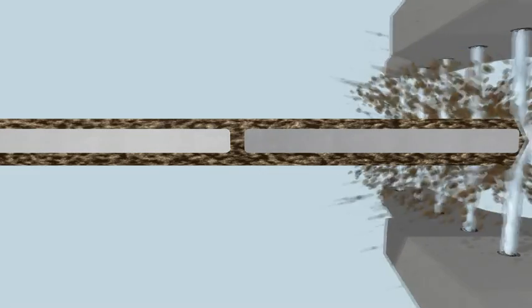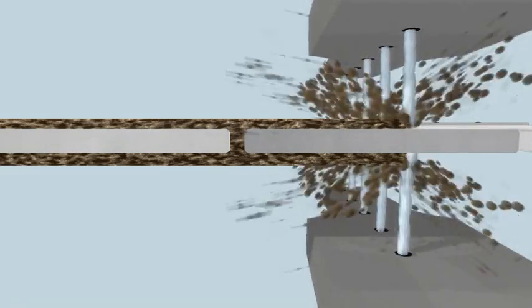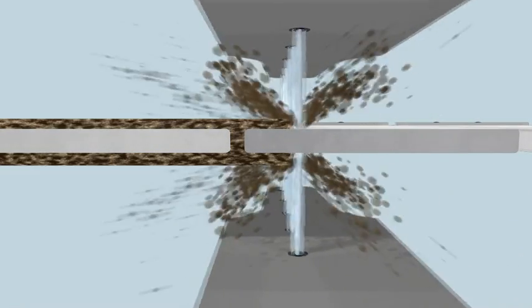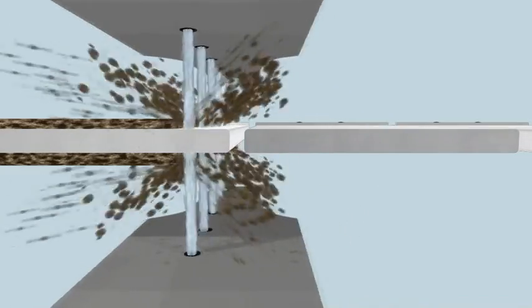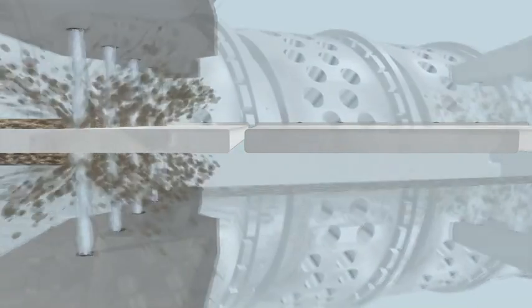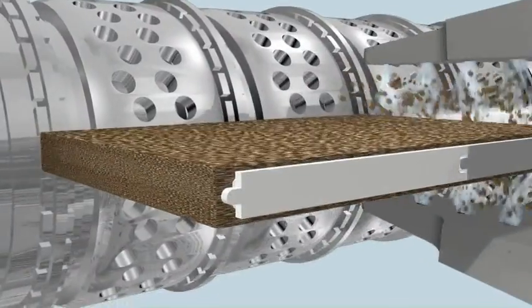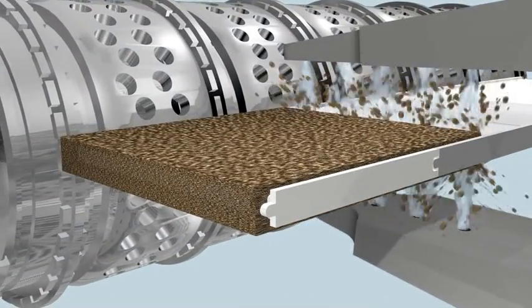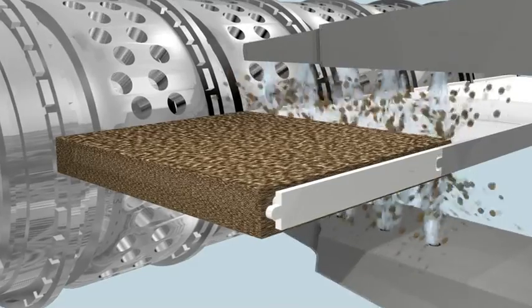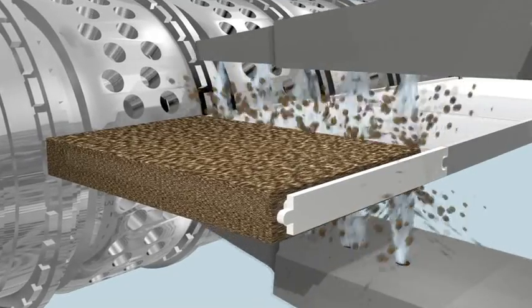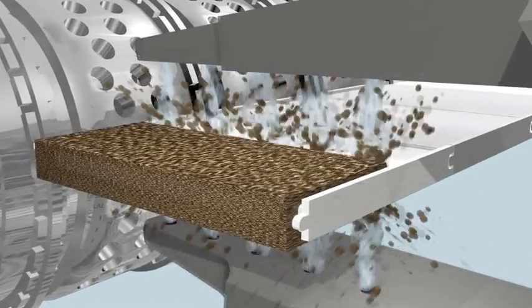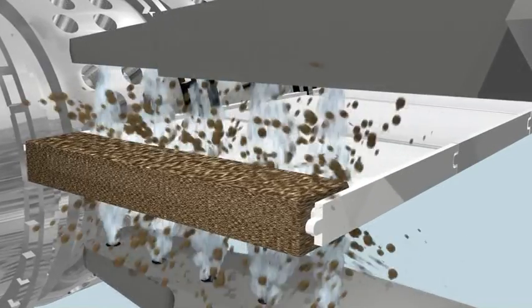Each spray nozzle creates multiple jet streams. The layer of thread and the water jets are designed so that the water jet passes through the layers, hits the plastic wall, and is forced backwards. This creates a powerful spot back flush, which carries with it the trapped particles and the filter cake out of the cassette's thread layers, and through the open drain control valve, to the gravity drain system.